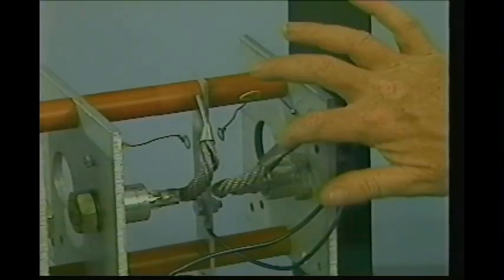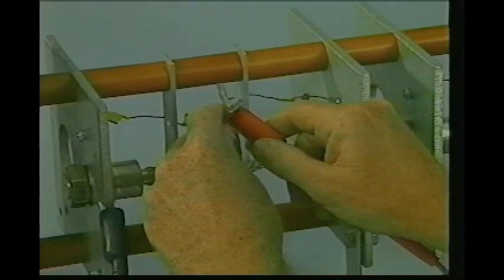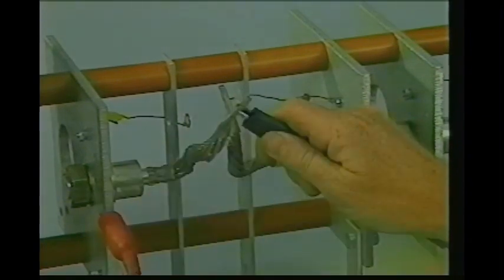The test procedure began with the isolation of the diodes from the rectifier by removing the pigtails. The meter leads were then connected to the stud and pigtails. Readings were then noted. The leads were reversed, and once again, readings were noted. After testing all of the diodes in the rectifier assembly, the results were evaluated.